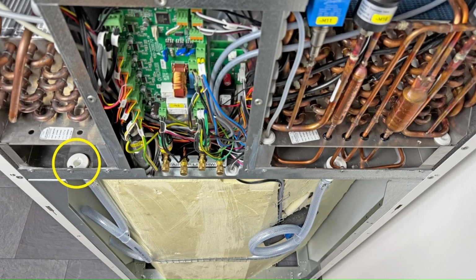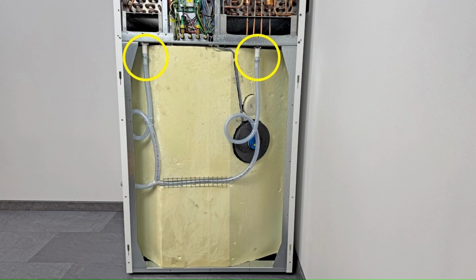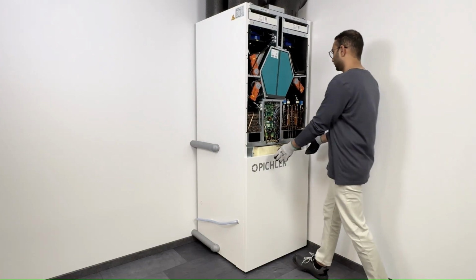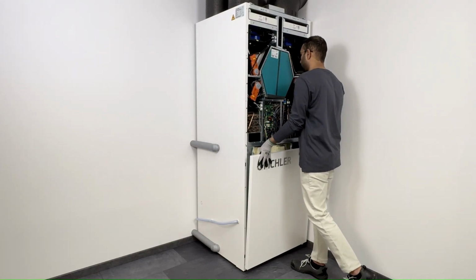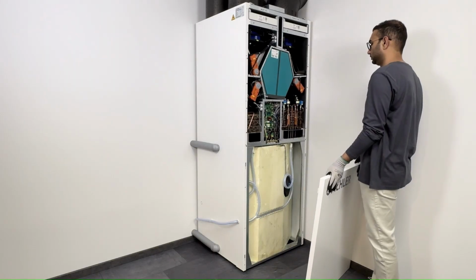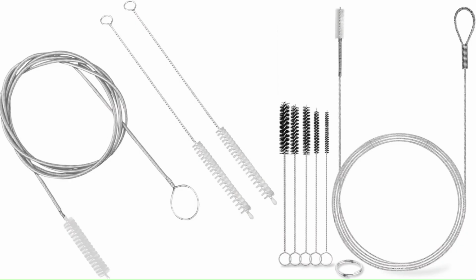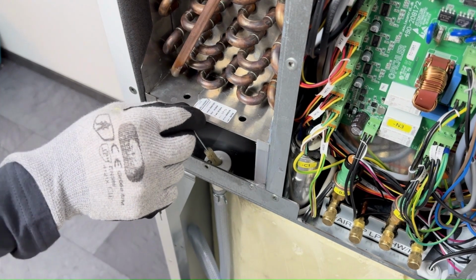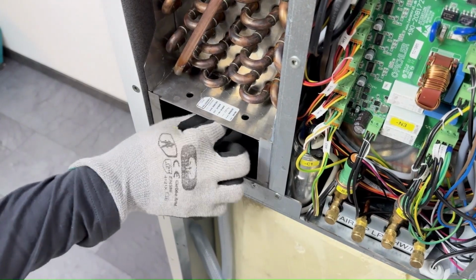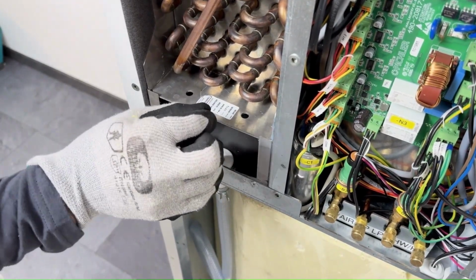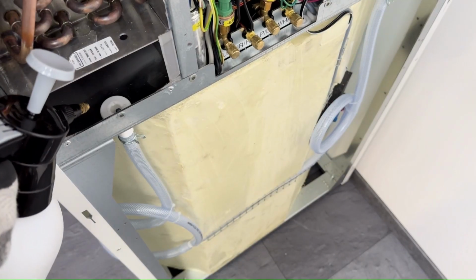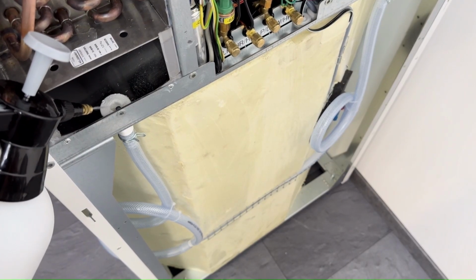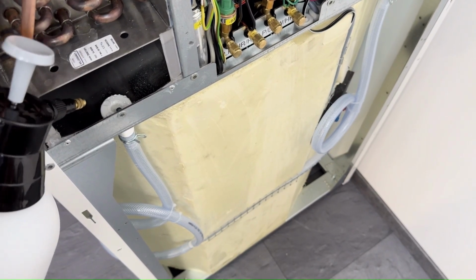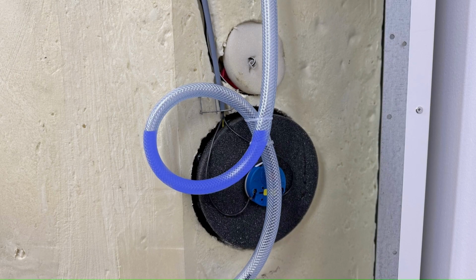After cleaning the heat exchanger and the condensate trays, the condensate drains must also be cleaned. First, open the front cover of the hot water storage tank so that the condensate hoses are clearly visible. Use a flexible drain cleaning brush, as shown on the screen, to carefully remove any deposits or blockages in the condensate drains on both the exhaust air and supply air sides. After cleaning, test the condensate drain, fill the tray, check the water flow and make sure there are no leaks. Fill the odor trap with water before recommissioning to prevent bad odors.